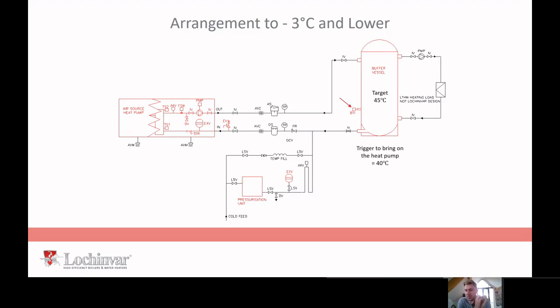The heat pump is going to be using compressors. With compressors, they have a big current draw to turn them on, and then to make them run efficiently, you want them to run for a long period of time. So you want to turn it on and keep it running. You can't do that with a system which has a low content, unless you've somehow perfectly matched your loadings. But that's pretty much impossible because the heat pump performance changes as the outside air temperature changes. So we have a thermal store, and that's going to be anything from 10 to 20 litres per kilowatt of air source heat pump, as a rule of thumb.